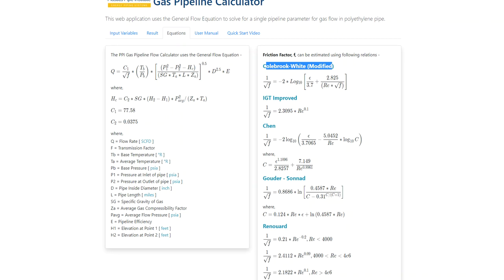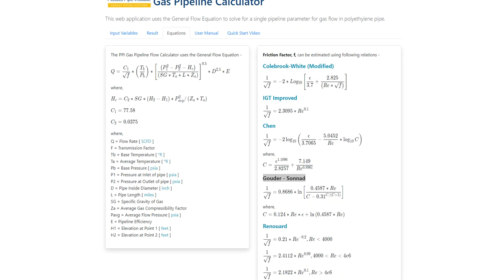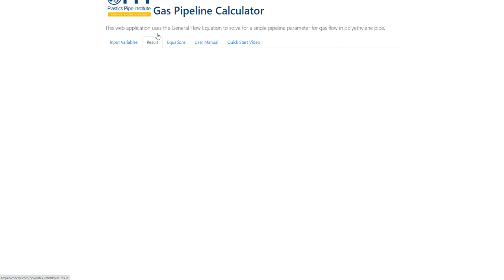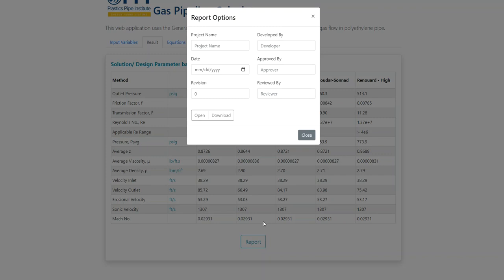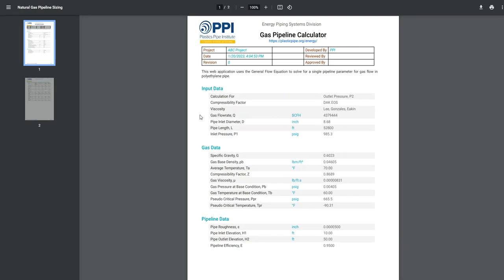Table 5.1 of the user's manual lists many methods for estimating the friction factor and the limits for their applicability. The gas calculator presents results based on the following transmission factors: the Colebrook-White modified, the IGT improved, the Chen method, the Gouder-Sonnad method, and the Renouard method. Going back to the results tab, a report can be generated by selecting the report button. Project data can be entered, and the report can be downloaded or opened. The report summarizes all the input variables and the calculated variables.